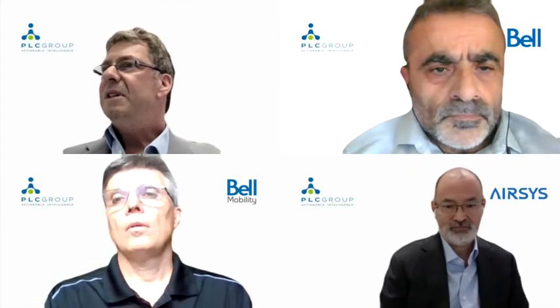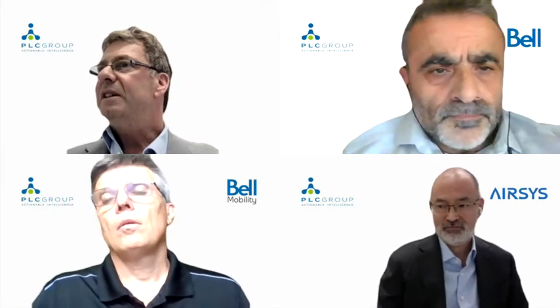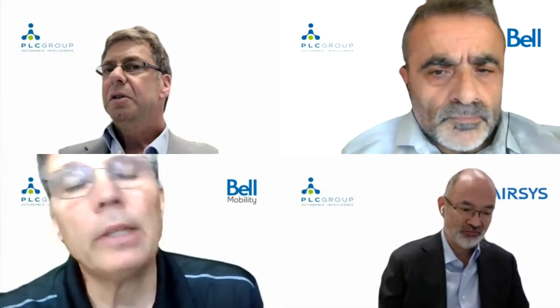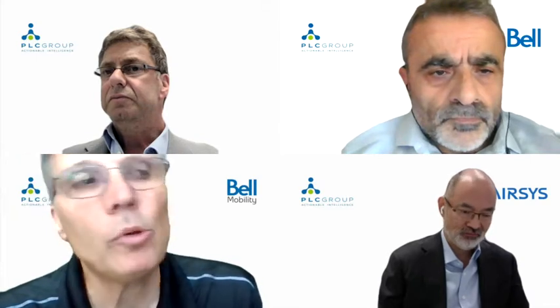Hi, Tony. Would you repeat the ratios you mentioned for free air cooling and mechanical? Sure. Generally speaking, I think mechanical is about 3 to 1, whereas free cooling we rate differently. It's a simple straight line linear formula between CFM and temperature differential. But roughly speaking, it's going to be 10 to 20 to 1. So 200 watts of fan can deal with 2,000 watts or even 3,000 or 4,000 watts of heat load.